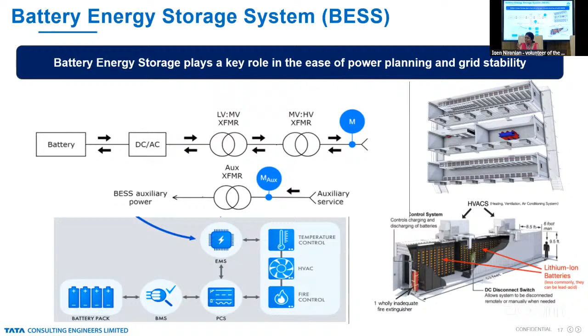The main components of a battery energy storage system are the battery, a converter, and a transformer, since the output has to be converted to a voltage grade suitable for connecting to the grid. That's called an inverter duty transformer, followed by a power transformer that allows connection to a grid of 132 kV, 220 kV, 400 kV, or even 765 kV. Like any system, it also has auxiliary systems to run its own auxiliaries. In the top right corner you can see the layout of a battery container. There are different types of battery containers, standardized, air cooled, and liquid cooled, with many design choices where we play a role in selecting the right solution.